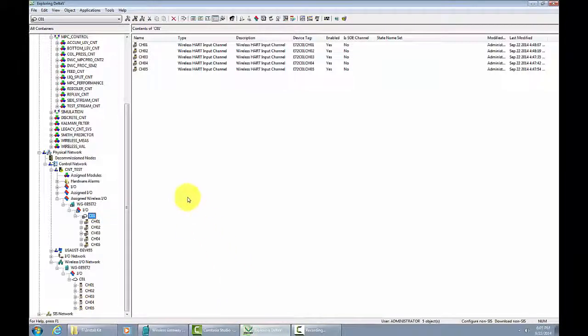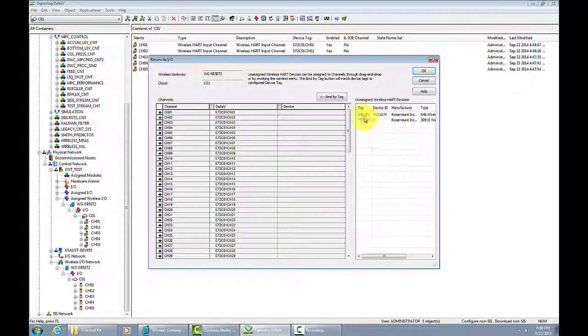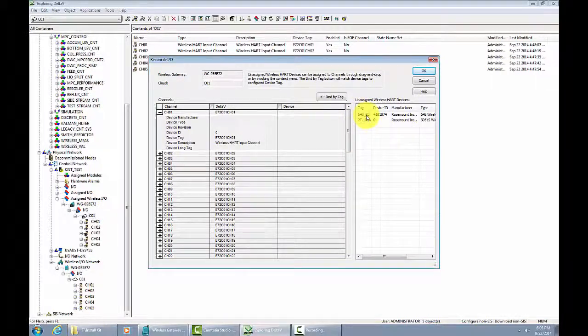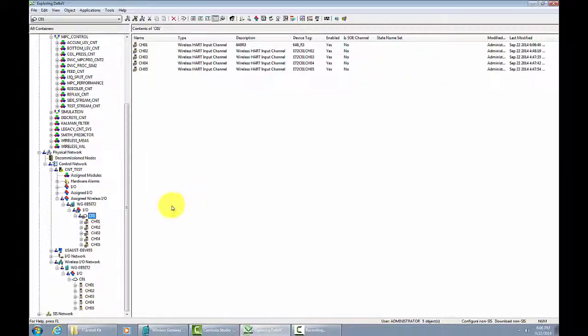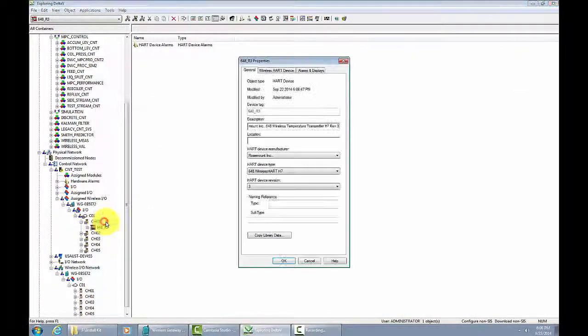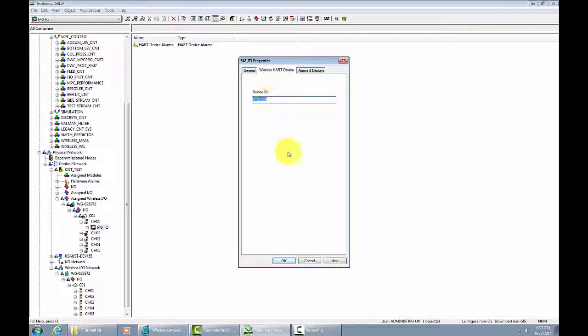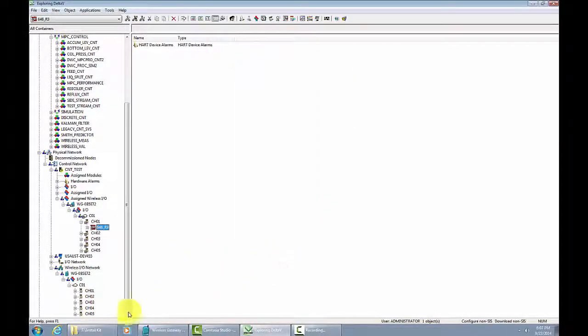So we'll switch over to the DeltaV Explorer, and what we need to do at this point is connect that device to the DeltaV configuration. We do that through the Reconcile I/O, and we can see the device on the Reconcile panel. We drag that over to the device pane and it'll show up. We want to take the tag and descriptor from the device that we just configured and move those over. So we select them and they now show up under the DeltaV Explorer. And we can look at the details of the device, and we can see the tag. We can see it's 648. We can also validate the device by looking at its device ID.